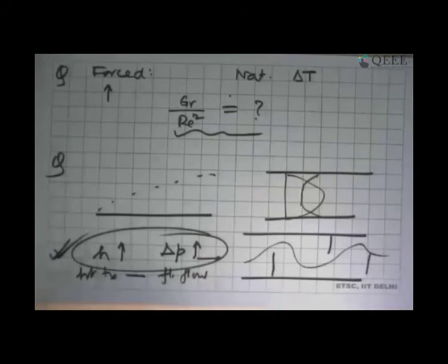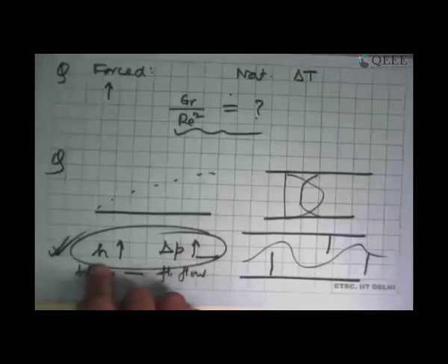So you have a penalty on the system design by way of more power consumption for pumping or blowing, while at the same time you got the advantage of a better heat transfer coefficient inside this. This is always a trade-off that is fundamental to all heat transfer equipment design. I have not talked too much about delta P, but in all the things that we have looked at, the skin friction coefficient is what was coming in, and through pipes and all we can calculate the pressure drop and the heat transfer coefficient.